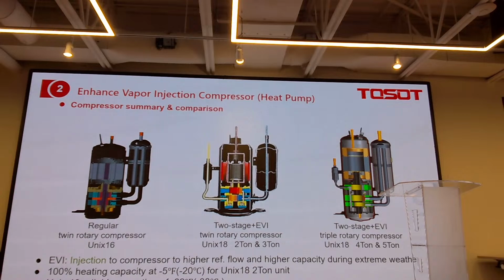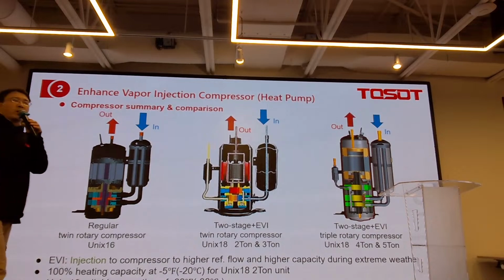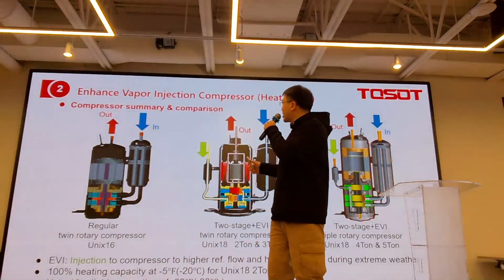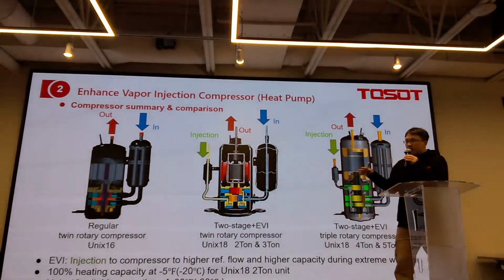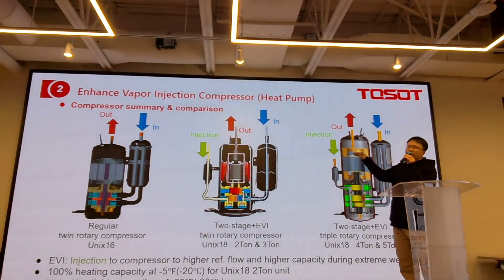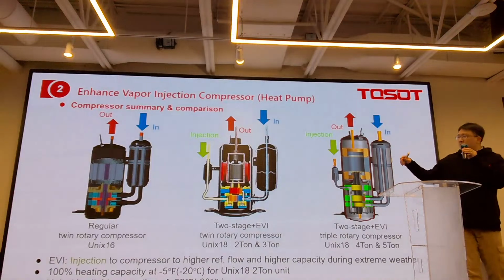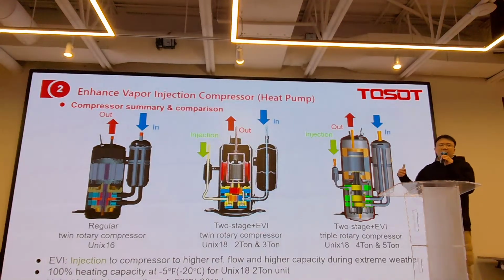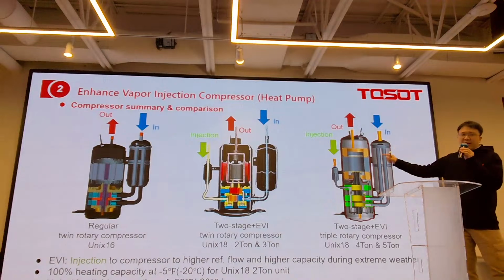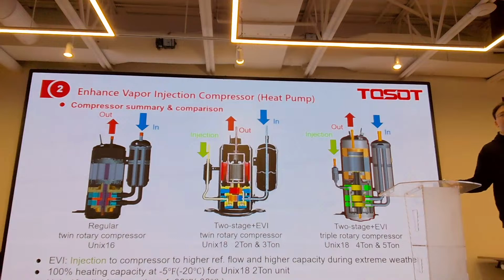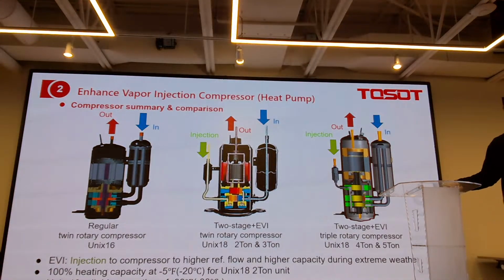Okay, the reason is that the regular or high standard compressor is just one in and one out, right? However, when the outdoor ambient is low, we still need the high pressure to be very high. But if the outdoor ambient is low, the pressure difference of this compressor will be very high. In other words, the refrigerant flow rate would be extremely low. And what is the consequence if we make the refrigerant flow rate very low?